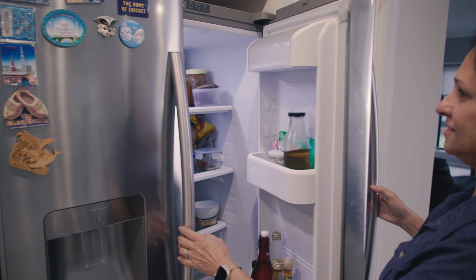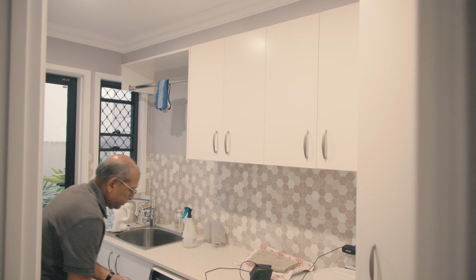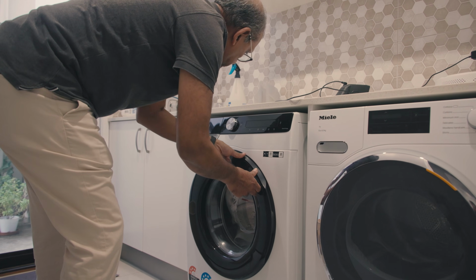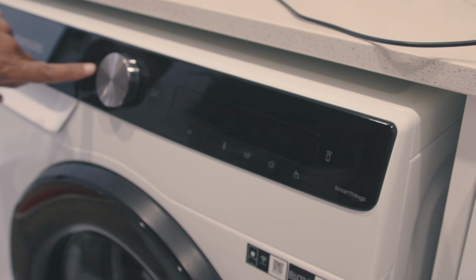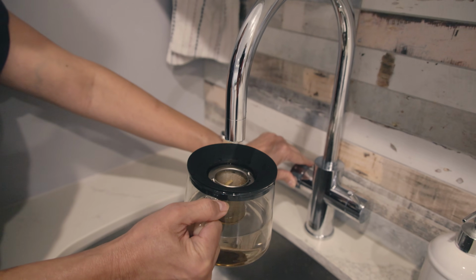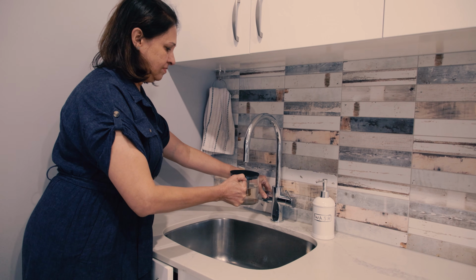The 20 kilowatt inverter definitely has helped me switch on multiple loads at the same time, and it did really come to the fore when we tested the system, when the installer asked me to turn on all the electrical appliances and the loads. So we had the aircon running, the oven running, and probably the sauna as well. It really went well without tripping or causing any issues.